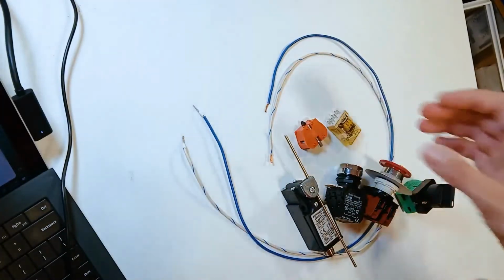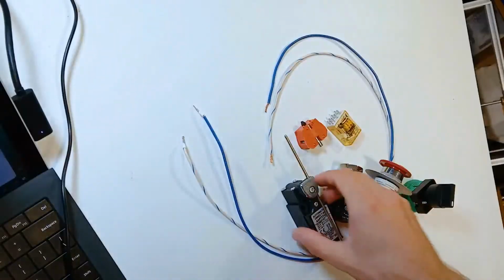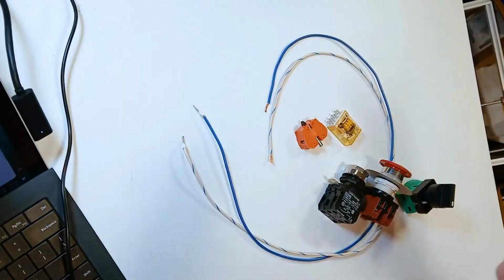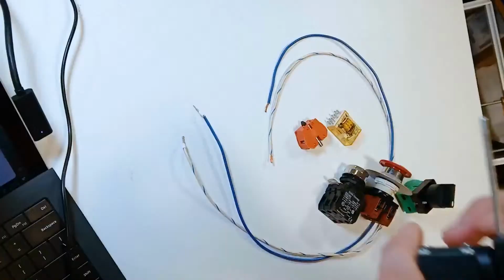One common factor about all of these electromechanical switches is that there's some sort of moving part involved. We can hear a click, we can feel something move, and that mechanical motion means that inside, a piece of metal is simply touching another piece of metal. Could be due to an electrical coil, it could be due to, like with the limit switch, some sort of external force applied on the side of it, and that gives us that motion that we need, and often accompanied with a click sound that we can hear to assure us that the sensor is actually doing its job.